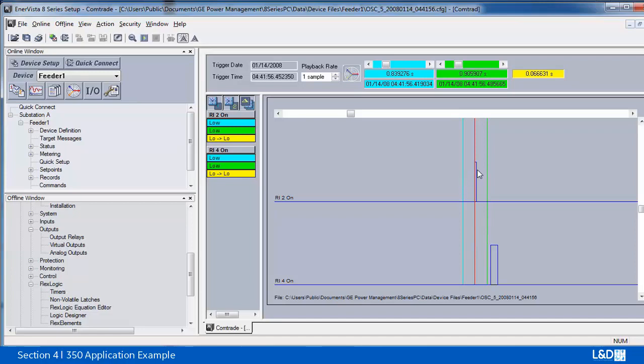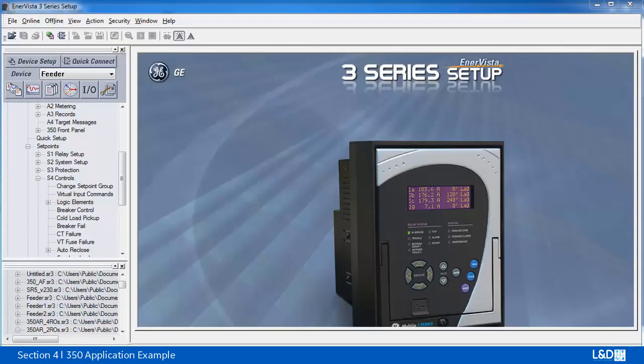So once the reclose turns on the virtual output 1, it turns on the auxiliary 3 and 4. This will apply the current, and this will cause the 350 to trip. Come back, 350 publishes a remote output message to the 850, received by remote input 4 of the 850. So that's how this whole process works. That's the demo of the auto reclose using the GOOSE message between the 350 and 850. 350 publishing 4 remote outputs and received by 850 as the 4 remote inputs.